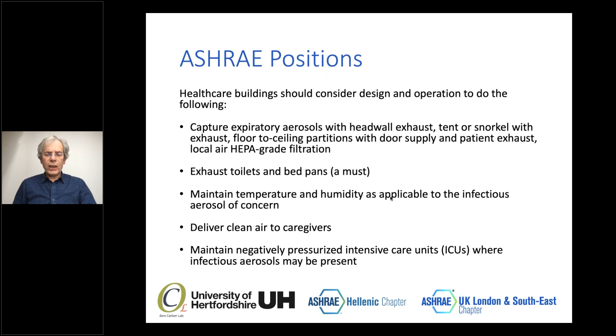A number of temporary facilities have been created across Europe to deal with the pandemic. And there are large open areas, rooms where patients are going to be situated. However, this is going to increase the spread of disease simply because if you just look at these recommendations, floor-to-ceiling partitions with door supply and patient exhaust need to be installed there, and these temporary facilities don't have that. Exhaust in toilets and bedpans is a must, and we need to maintain temperature and humidity control as applicable to the infectious aerosols of concern. We need to deliver clean air to caregivers, to staff who are working at the front line, and maintain negatively pressurized intensive care units where infectious aerosols may be present.